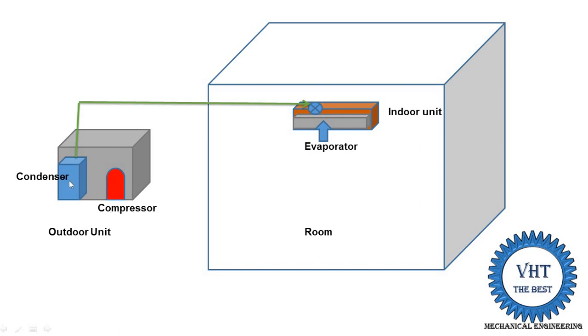In the compressor, compression takes place; the refrigerant is then supplied to the condenser where heat is rejected, followed by expansion. The blower of the evaporator sucks air from the upper side of the indoor unit. Room air passes over the evaporator, gives heat to the refrigerant, gets cooled, and is then supplied back into the room to handle the room cooling load.